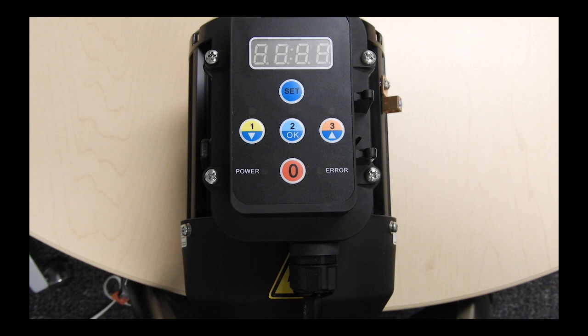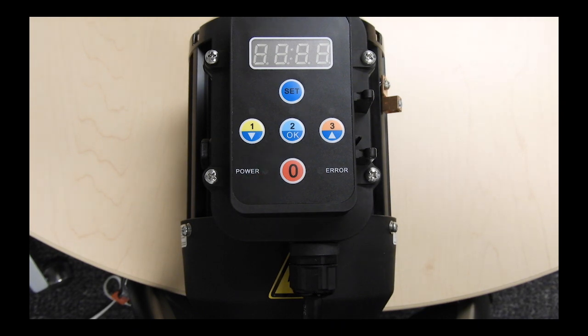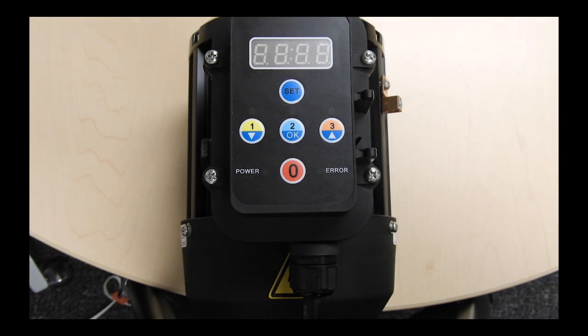Any time the pump is started from the off position, it will run through the priming cycle. The default is 1000 watts or full speed for 2 minutes. The priming power level and time can both be adjusted.